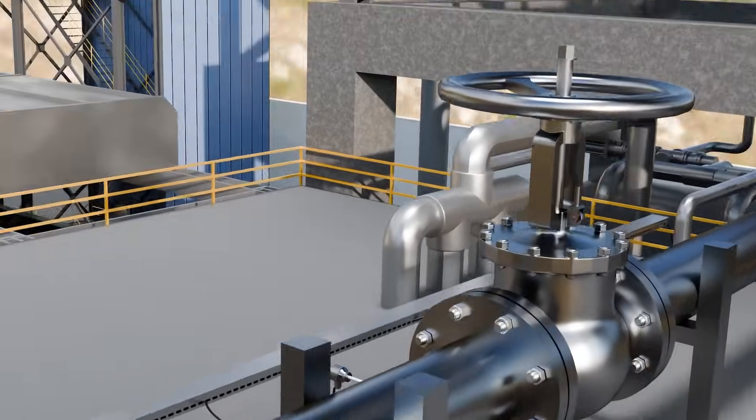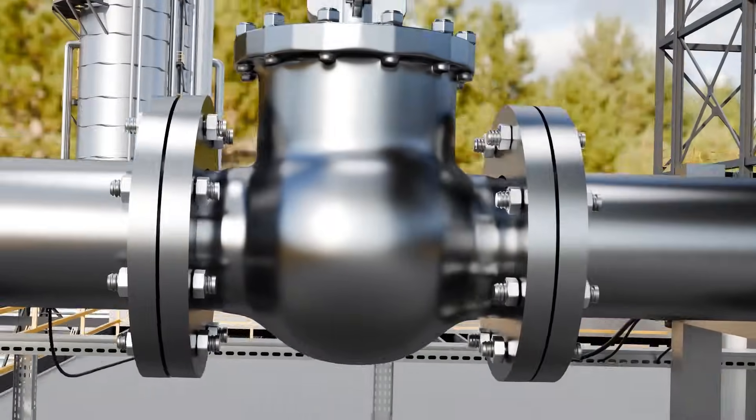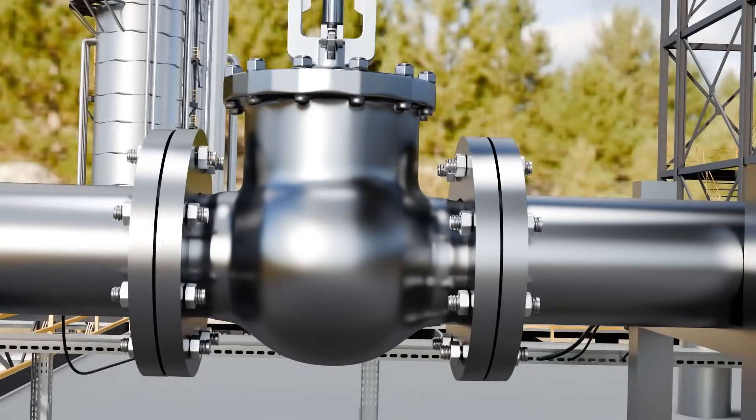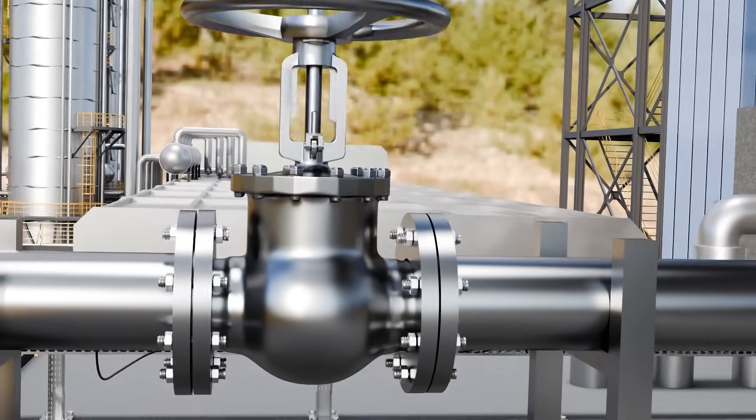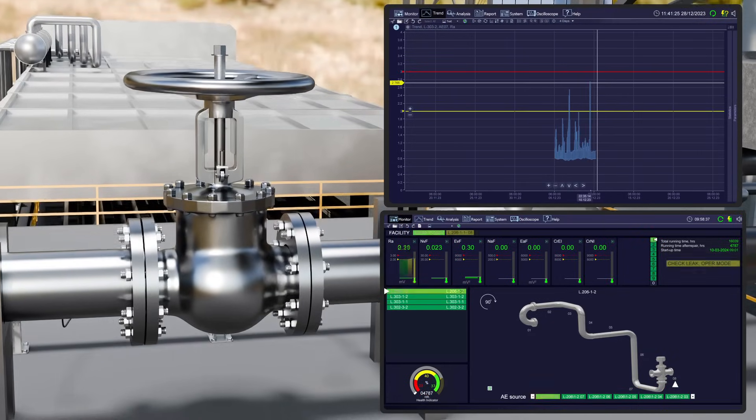The leak began to grow, threatening severe consequences if it had not been addressed promptly. Thanks to the compact system, the leak was identified in a timely manner, as the acoustic emission method allows the early detection of such anomalies.